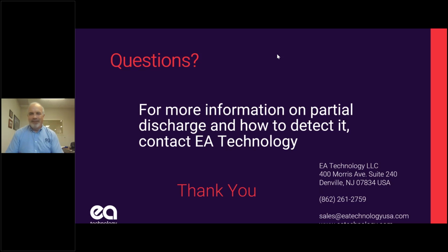Yes, that's right. So if you have an unshielded cable and you bring a non-contact voltage sensor up to it, remember that picture, the electric field extends out past the insulation. So the non-contact sensor, which is a field sensor, picks up that field. If I put a shield around that cable, I now have that electric field contained within the shield. And so if I go to that shield or outside that shield with a non-contact sensor, I'm not going to see anything. The shield is ground and the shield is safe to touch and the sheath is safe to touch. But obviously if you start digging into there or go to one of the ends, it's still live. Yeah.